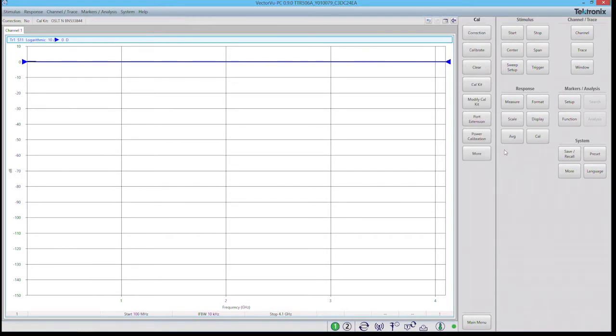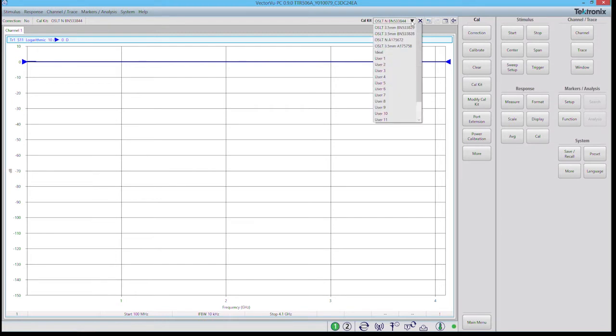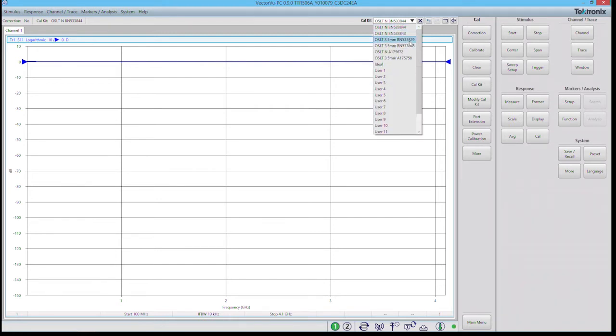Now we define the cal kit that we like to use. So under the sub menu we select cal kit, and our pull down has a number of predefined cal kits that we can choose from. In our case we'll be using this OSLT type N BN 533 844 cal kit.